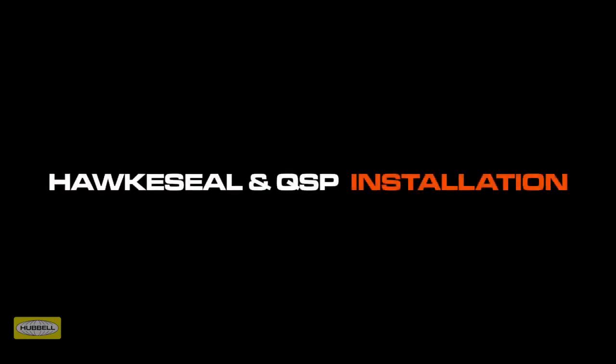The cable gland should already be prepared for putty compound installation as per the assembly instructions. During gland installations, we recommend removing the rubber resin dam before installing the spigot or diablo components.